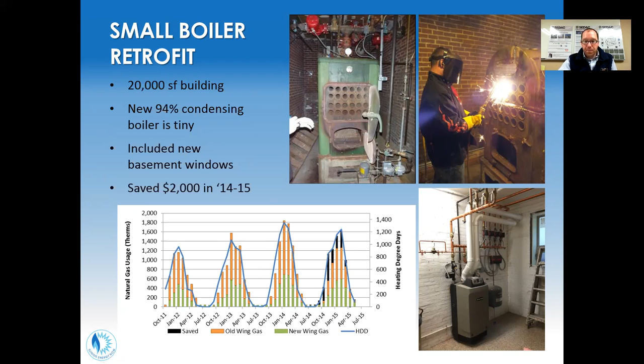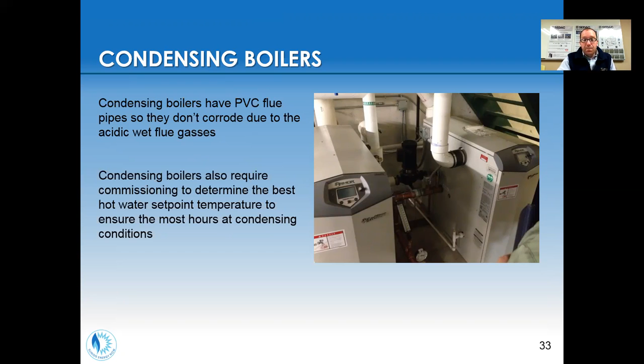Another photograph of some condensing boilers of a different type. Notice again, they have PVC flue stacks, so they don't corrode due to the acidic condensate. A good point to make is that all condensing boilers require commissioning and making sure that the boiler set point temperature is varying based on the outdoor air temperature, to make sure that you have the most hours at condensing conditions. There'll be some hours of the year where they're having to produce very hot water to heat the building, and some of those hours they're not even operating in condensing mode, they're operating in more of a standard boiler mode to produce 180 degree water, for instance. But for all the mild days of the year that they can produce 110 degree water or 100 degree water, then we're really getting down into the peak efficiency of those boilers. So making sure that the water set point is set up and stays in place over time is really crucial to make sure that you're getting a full return on your investment in these boilers.